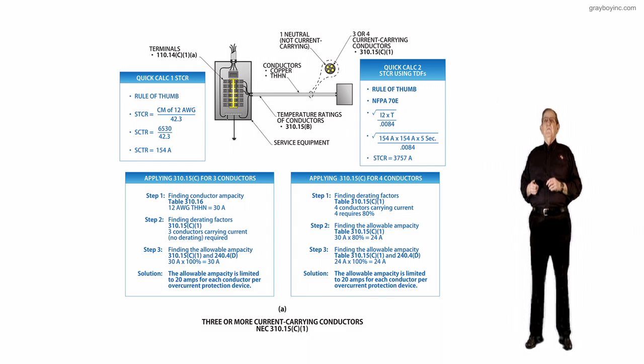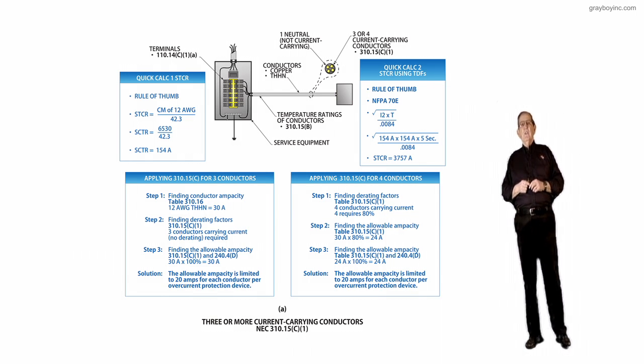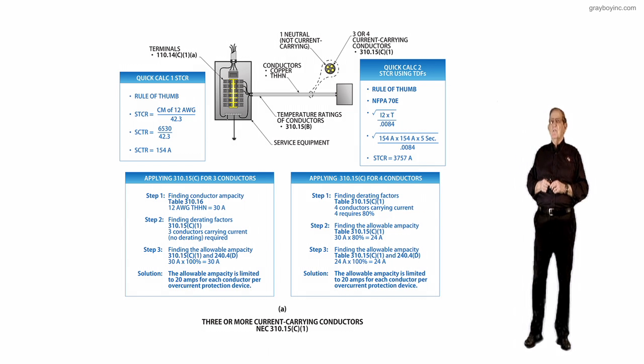If you look at the conduit in the boxed-in dotted area there. First, we have three or four current carrying conductors, 310.15 C1. Secondly, you have one neutral that's not current carrying, so you only have three conductors in there that would be considered current carrying.